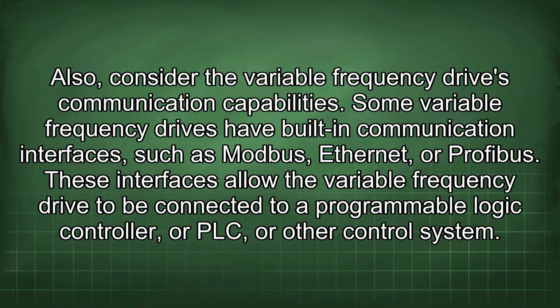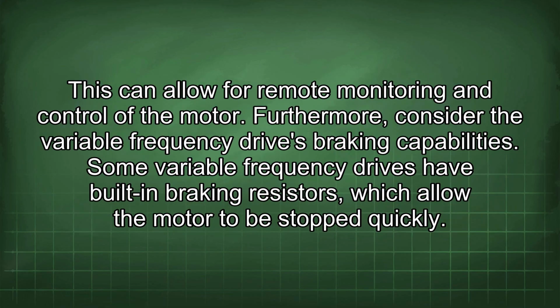Also, consider the variable frequency drive's communication capabilities. Some variable frequency drives have built-in communication interfaces, such as Modbus, Ethernet, or Profibus. These interfaces allow the variable frequency drive to be connected to a programmable logic controller, or PLC, or other control system. This can allow for remote monitoring and control of the motor.